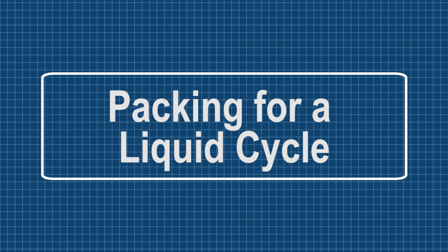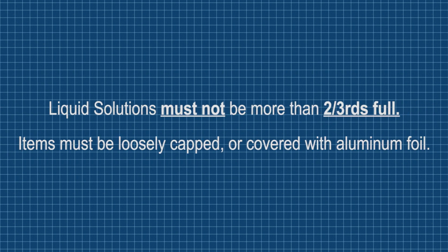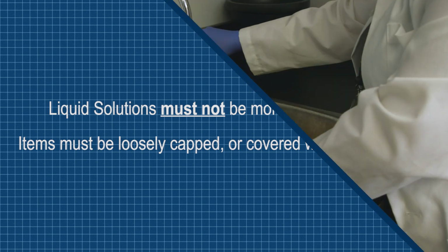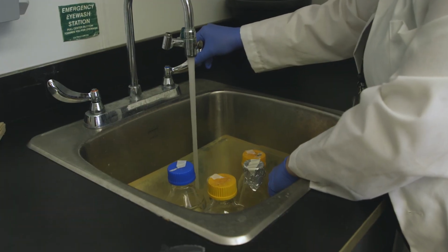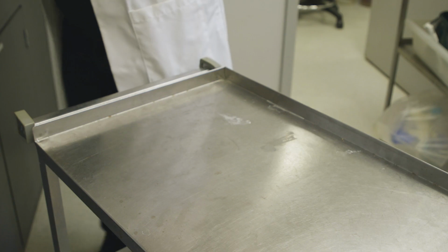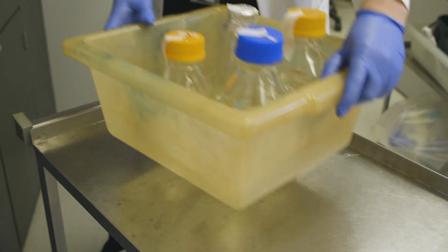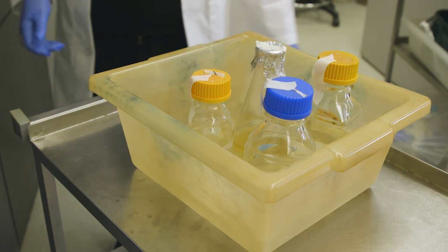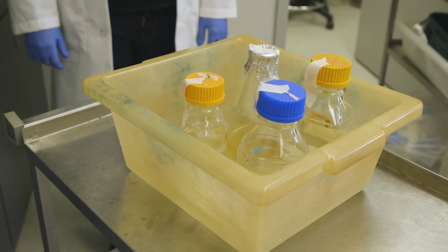Now let's look at how to package items that you would run through a liquid cycle. Liquid solutions must not be more than 2/3 full. Make sure to cover the solution with aluminum foil or have the tops loosely capped. The liquid solution must be placed into an autoclave bin that contains water. This water basin will help ensure a controlled decrease in temperature for your liquid solution upon removal from the autoclave.